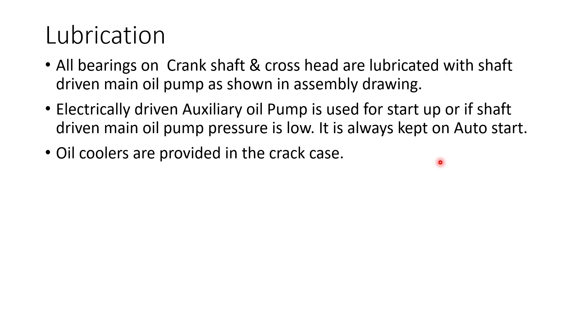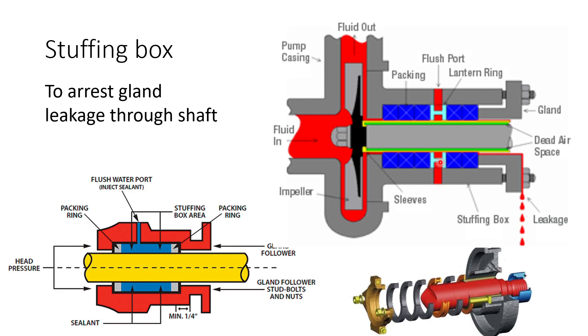Now let us talk about lubrication. All bearings on the crankshaft and crosshead are lubricated with a shaft-driven main oil pump, which we will see in the assembly drawing. An electrically driven auxiliary oil pump is used for startup if the shaft-driven main oil pump pressure is low, and it is always kept on auto start. Water coolers are provided in the crankcase to cool the oil.